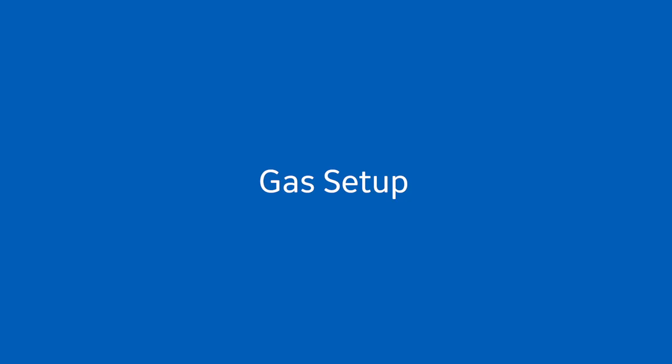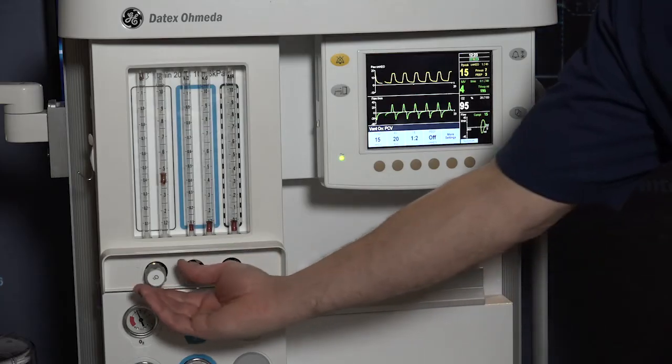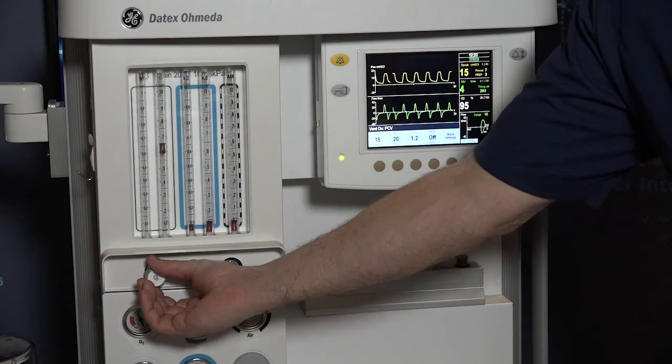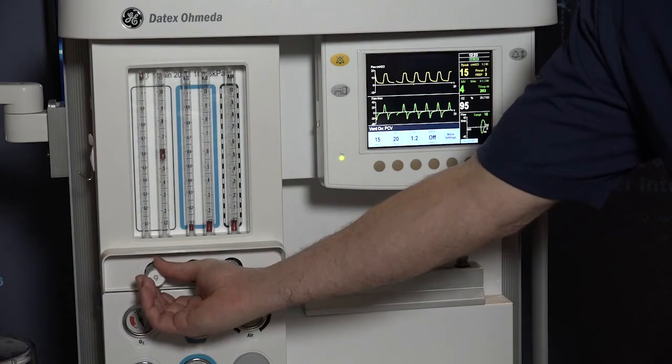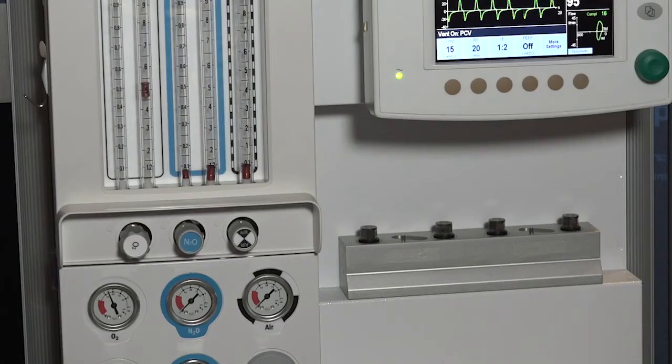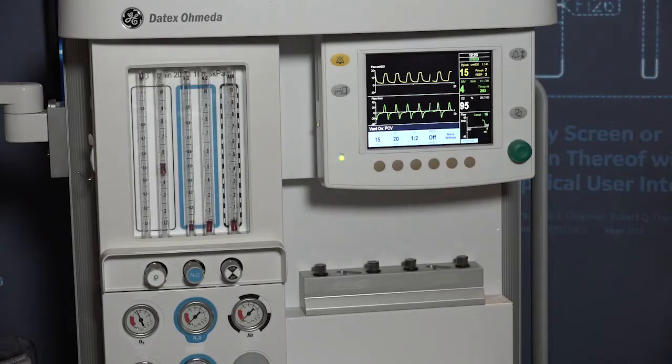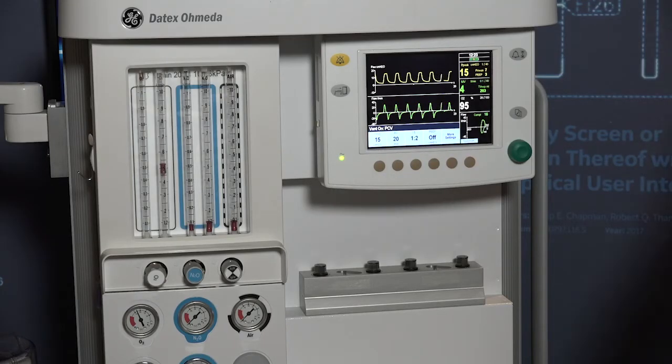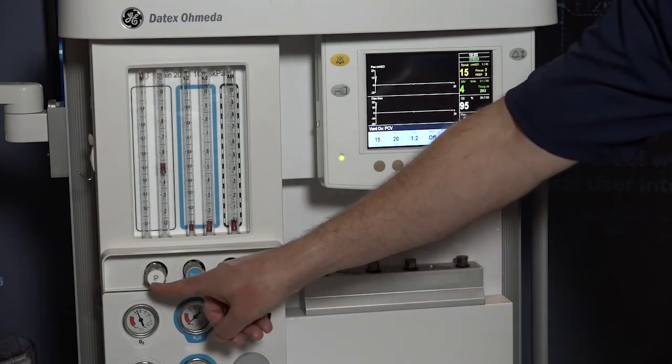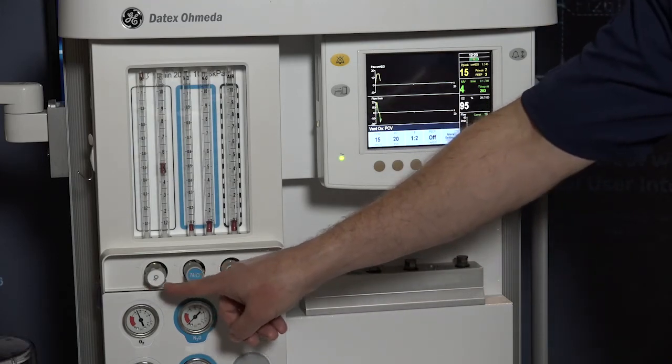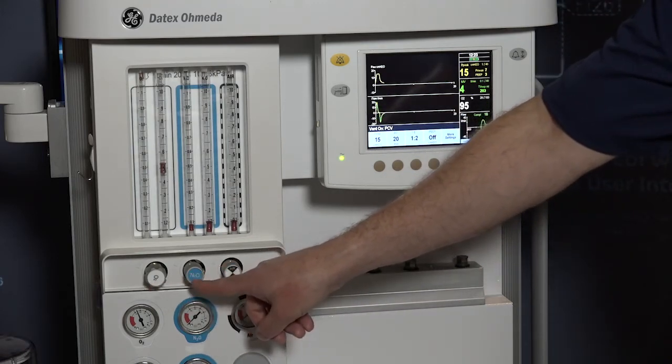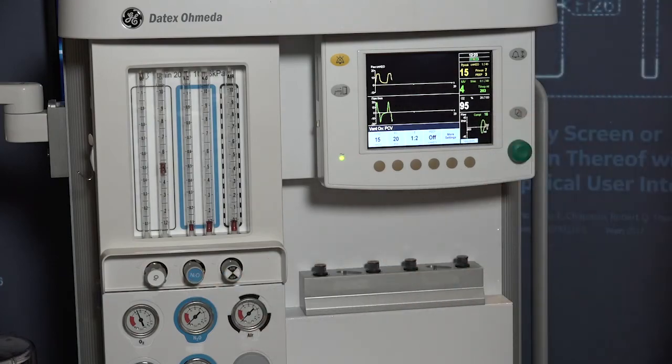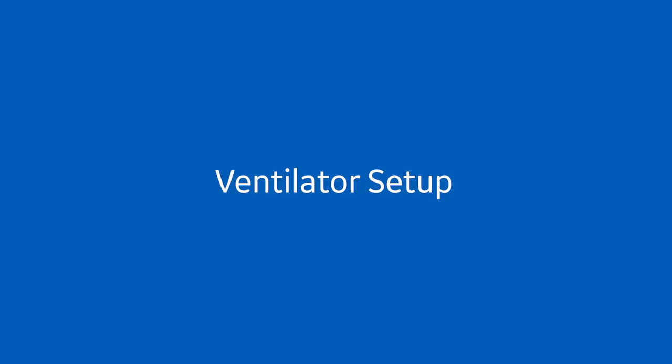To change the flow rates, adjust the air and oxygen flow knobs. The flows can be monitored from their respective flow tubes on the front of the machine. A gear linkage on the nitrous oxide and oxygen flow controls helps to keep the oxygen concentration higher than approximately 21% at the fresh gas outlet.